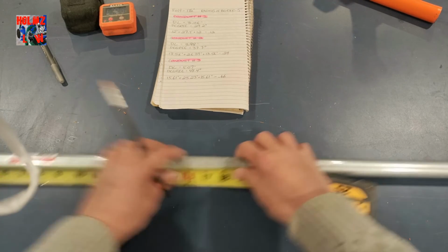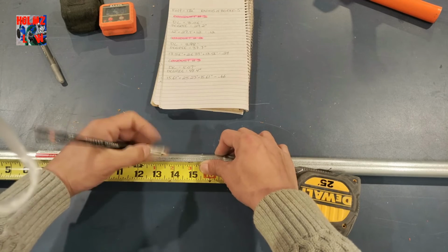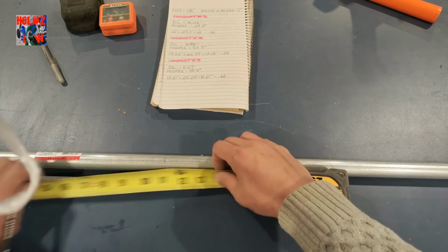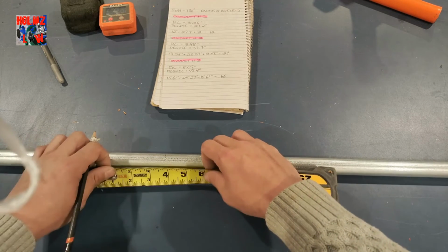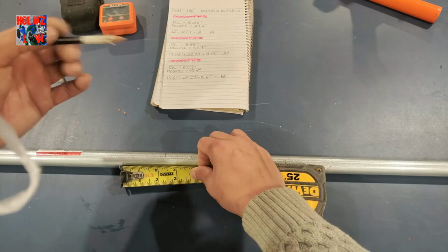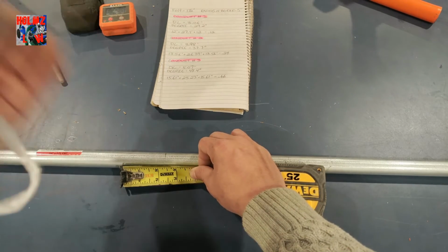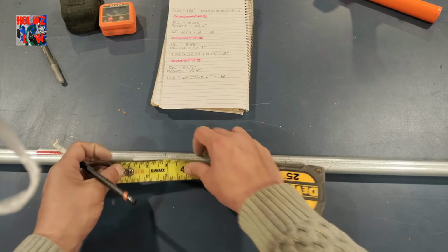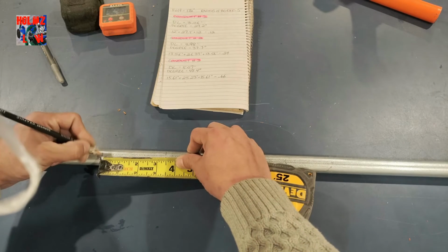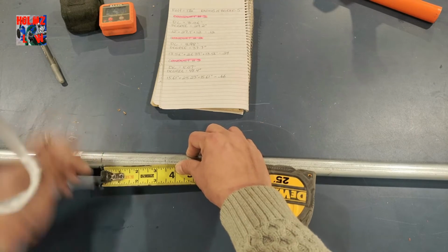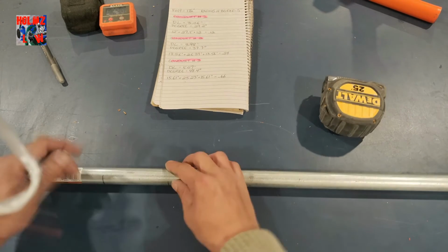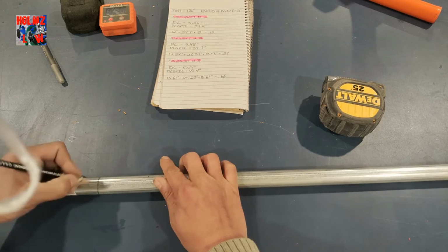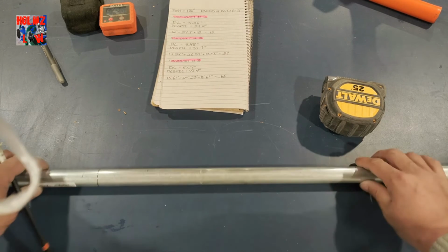13.5 inches is my first mark. 13.5. And my developed length is basically 4 inches, so I have to divide that in 2. 4 divided by 2 is 2 inches, plus my front of hook measurement. That's going to give me 3.5 inches from the center. Like I said, I'm going to start speeding this up now and doing the math in my head because we should all be on the same page by now. So this is my first mark where I'm going to bend, and that's going to be A.